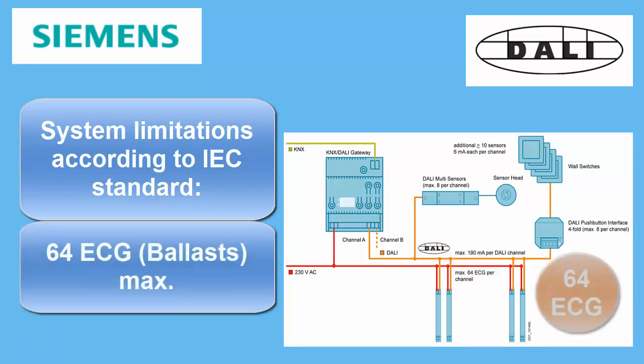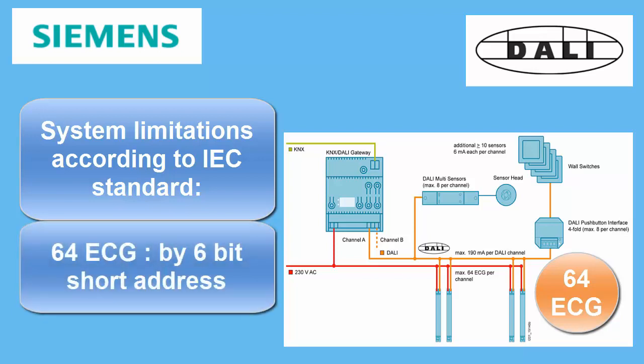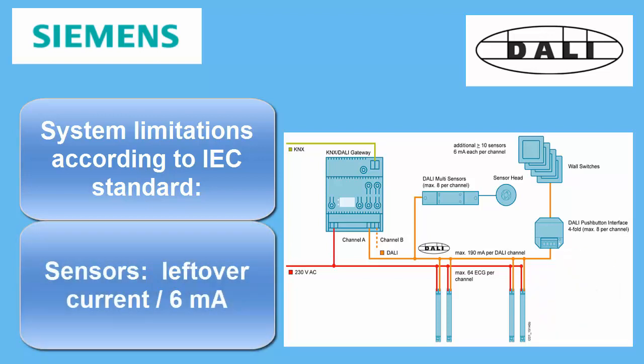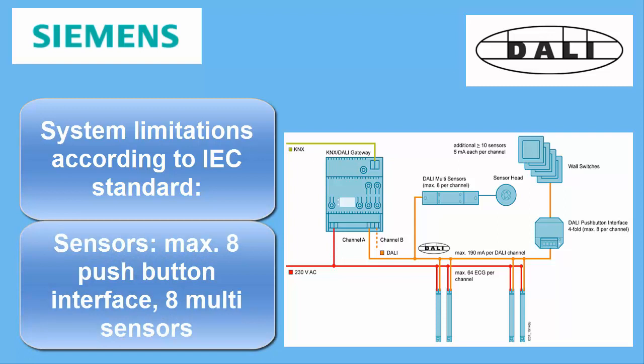The maximum number of ballasts on a DALI line is 64, represented by the 6-bit short address. There is no reduction in the number of ballasts for reasons of high current consumption, since the DALI standard requires ballasts not to exceed 2 mA each — so you can always use 64 ballasts per line. There can also be a number of inputs or sensors, which usually have a higher current rating than the ballasts, though the number of sensors has some limitations that normally won't be reached.